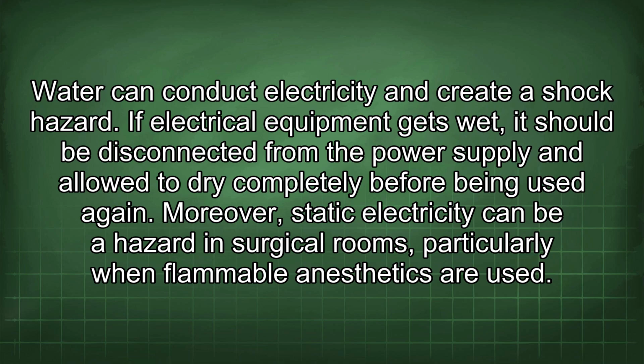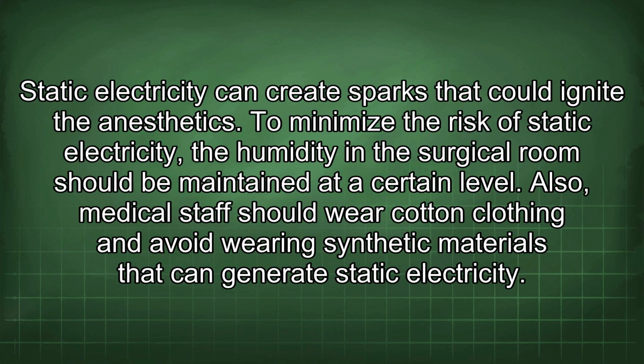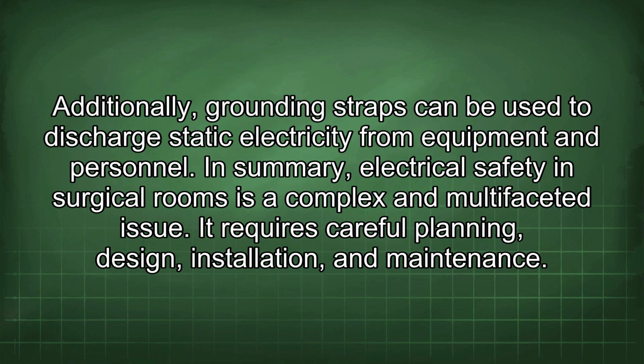Moreover, static electricity can be a hazard in surgical rooms, particularly when flammable anesthetics are used. Static electricity can create sparks that could ignite the anesthetics. To minimize the risk of static electricity, the humidity in the surgical room should be maintained at a certain level. Also, medical staff should wear cotton clothing and avoid wearing synthetic materials that can generate static electricity. Additionally, grounding straps can be used to discharge static electricity from equipment and personnel.